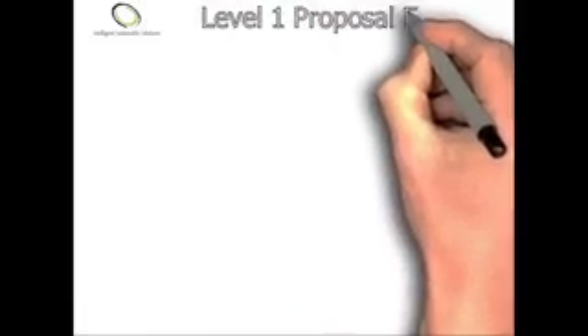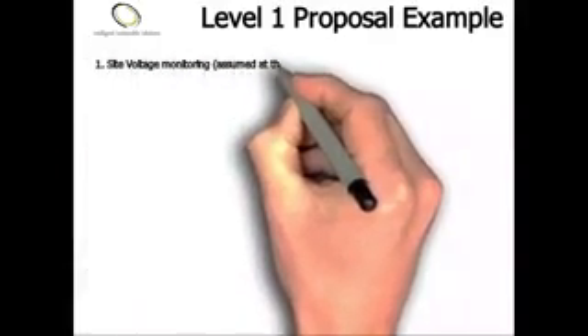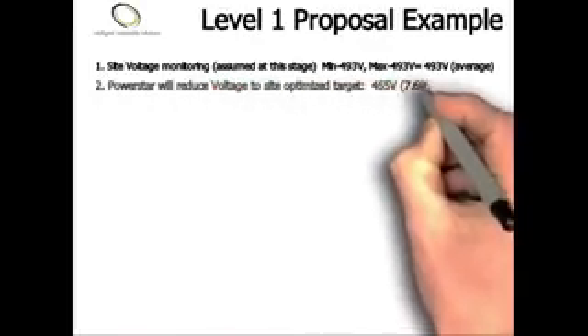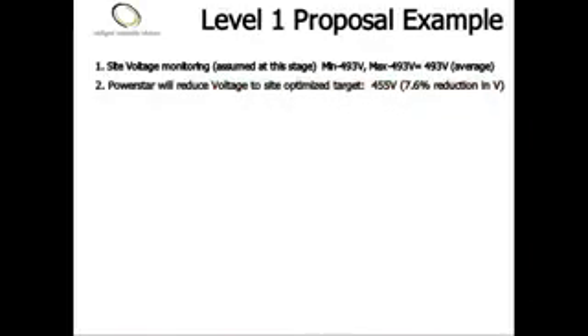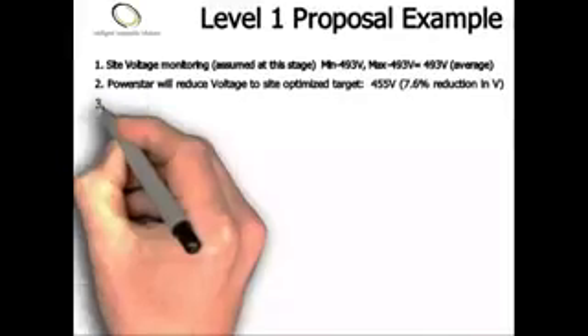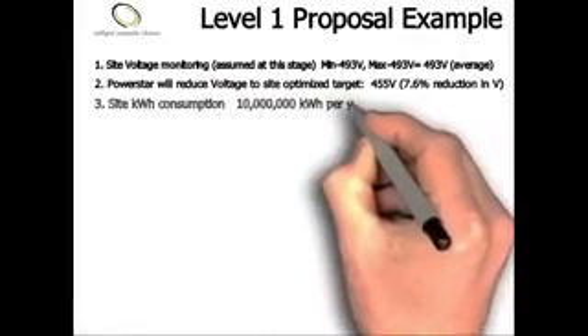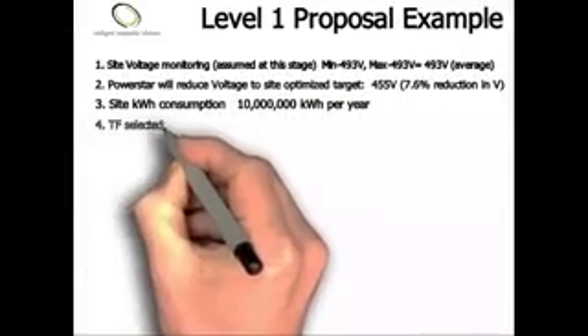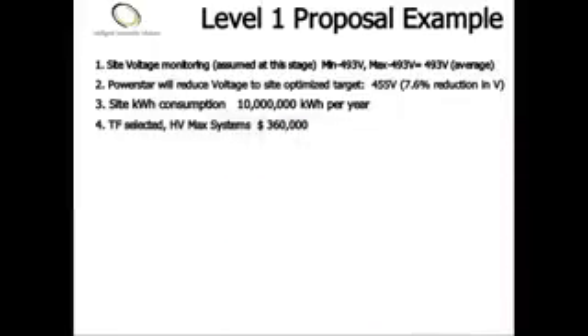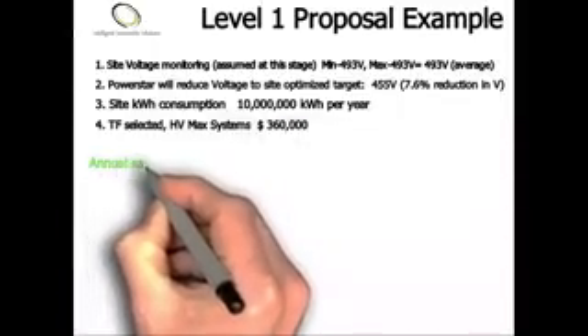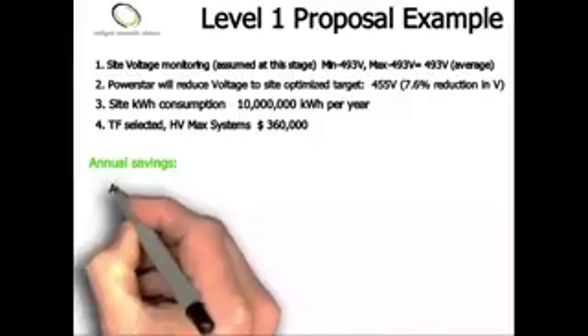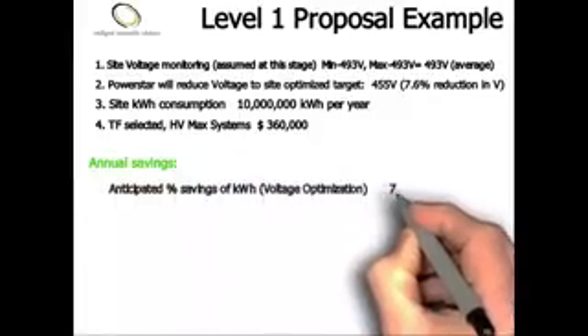Here's an example of how a Level 1 proposal would look. This will give an order of magnitude of what the opportunity savings could be before any site audit. 1. We start with the assumed average voltage of 493. 2. Installing the PowerStar system, we will optimize to the desired on-site voltage in this example of 455 volts, which is a 7.6% reduction in voltage. 3. We have taken a large facility with an annual consumption of 10 million kilowatt hours. 4. The budget proposed for the PowerStar equipment in this case is $360,000. If we annualize those calculations, we get the following.